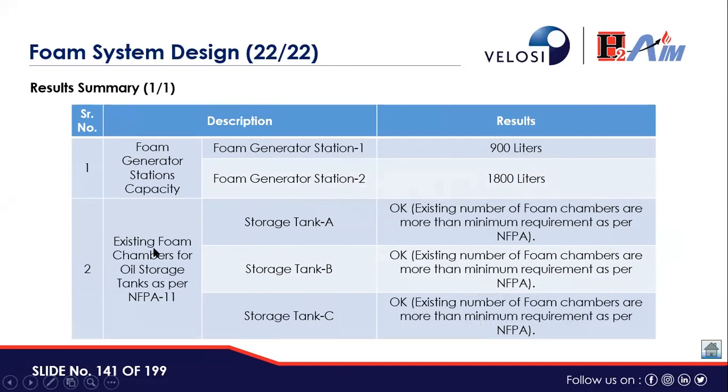For the existing foam chambers for oil storage tanks as per NFPA 11, storage tank A, the existing number of foam chambers is more than the minimum requirement as per NFPA. So these were the results. The number of foam chambers is more than the minimum requirement.